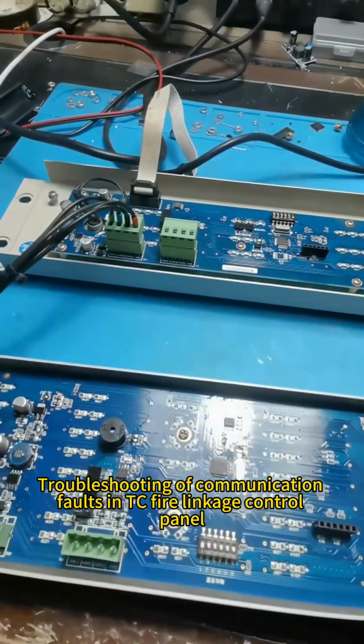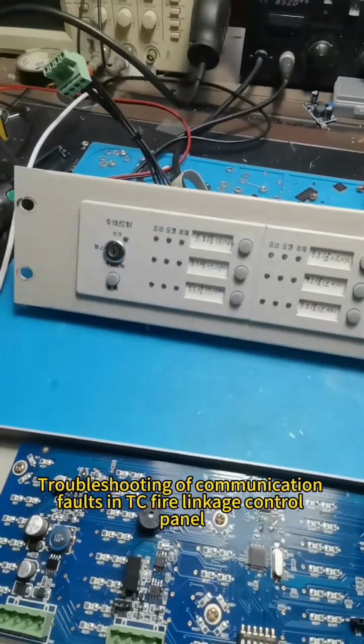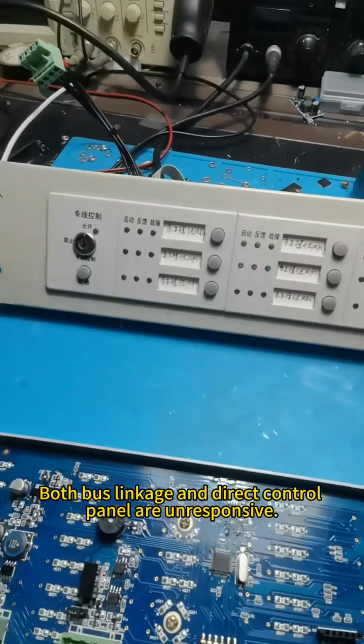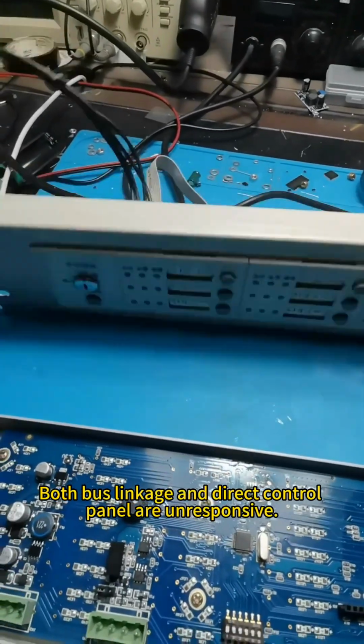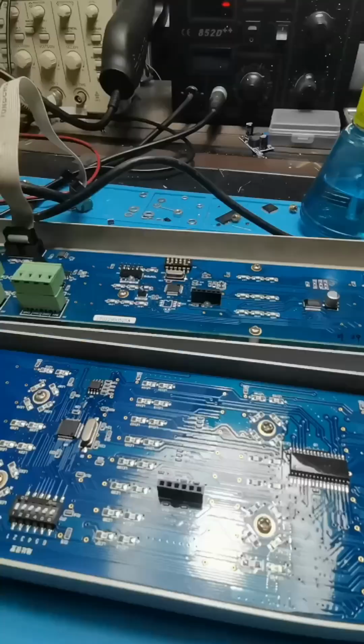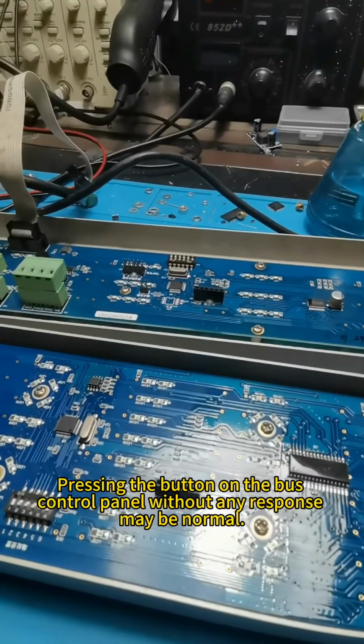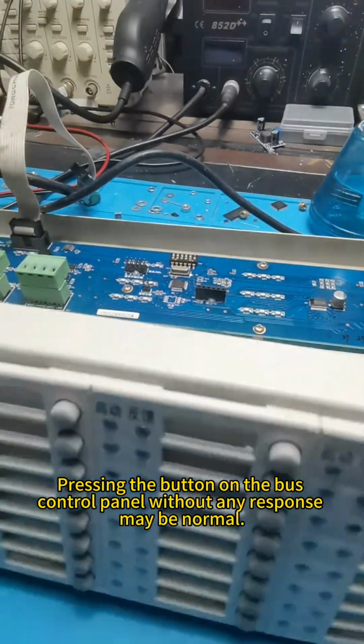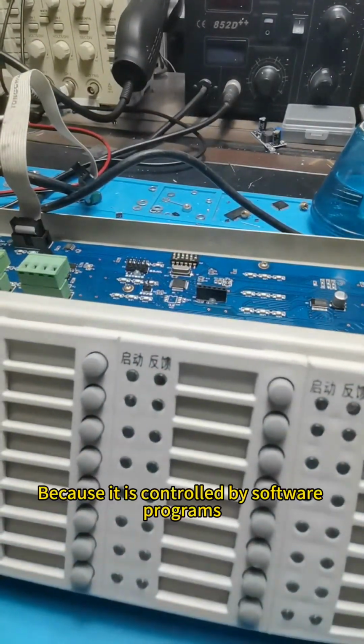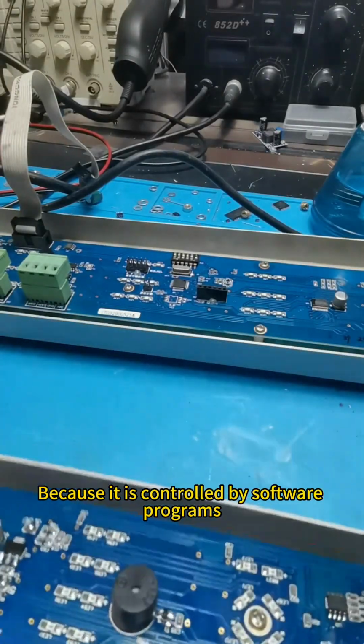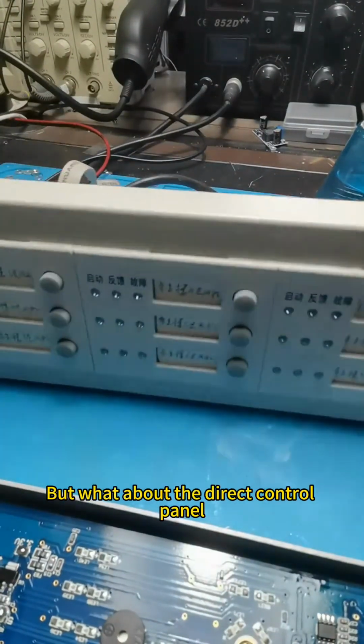Troubleshooting of communication faults in TC fire linkage control panel. Both bus linkage and direct control panels are unresponsive. Pressing the button on the bus control panel without any response may be normal, because it is controlled by software programs. But what about the direct control panel?